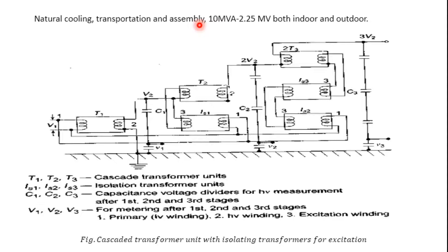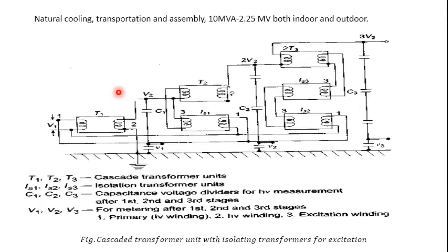A star and delta connection is possible with this method. Generally, testing transformers operating at 10 MVA in cascaded connection will give a high voltage output of 2.25 megavolts. It is possible for both indoor and outdoor applications. The limitation is that it requires too many transformers and is not fully reliable, but the advantage is that identical transformers can be used to raise the voltage.